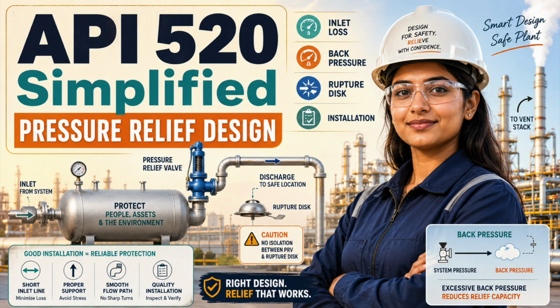Long inlet lines also create dead legs, trapped liquid, solids accumulation, corrosion pockets, and delayed pressure transmission. Relief inlets should be short, direct, and self-draining wherever practical. Avoid casually connecting process laterals to a relief valve inlet. Simultaneous process flow and relief flow can increase pressure loss and destabilize the valve. Where such a connection cannot be avoided, analyze the combined condition.